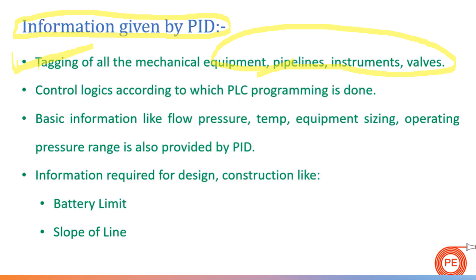A tag is basically the nomenclature — the name we give to a particular item in a plant. The tagging or nomenclature of every individual equipment or item that will be part of the plant is shown in the P&ID. The second thing is control logics. There are some dotted lines shown in P&IDs — those are control logics. The trip systems or on/off logics and on/off systems are shown with the help of dotted lines, and these dotted lines ultimately go to your PLC for PLC programming.